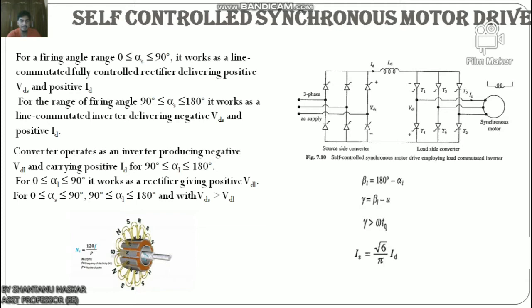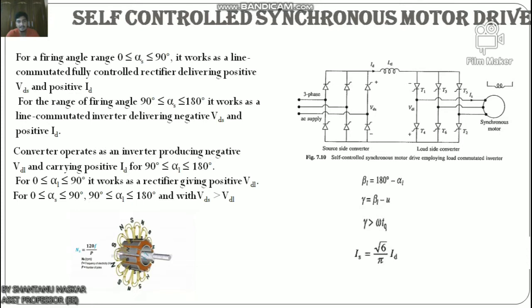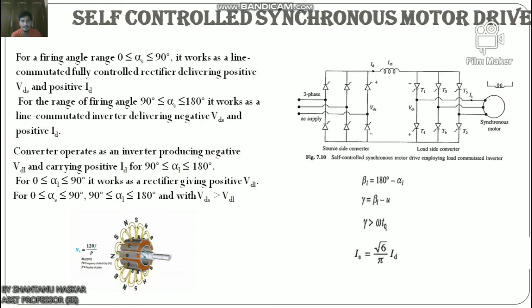If the commutation overlap of the thyristor under commutation is denoted by u, then the duration for which the thyristor is subjected to reverse bias after current through it has fallen to zero is given by γ = β1 − u. For successful commutation of the thyristor, γ > ω·tq, where tq is the turn-off time of the thyristor and ω is the frequency of motor voltage in radians per second. Since u is proportional to Id, for a given Id, β1 can be calculated such that the thyristor is reverse biased for a duration γ_min — just enough for commutation. This minimizes β1 and maximizes the motor power factor. Since γ is kept constant at γ_min, this control scheme is called constant margin angle control.